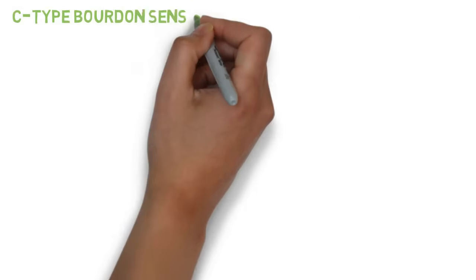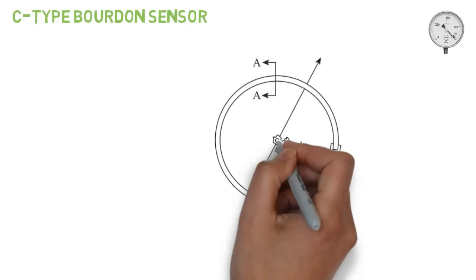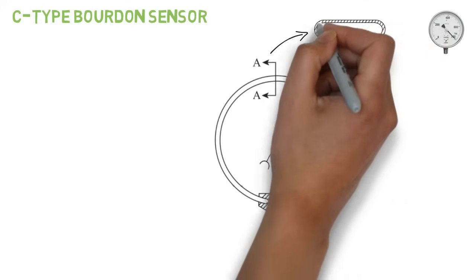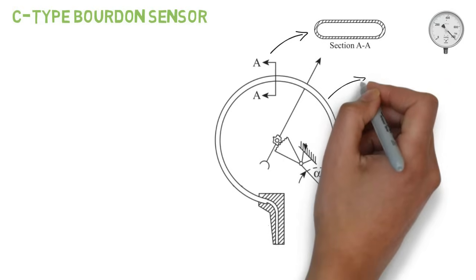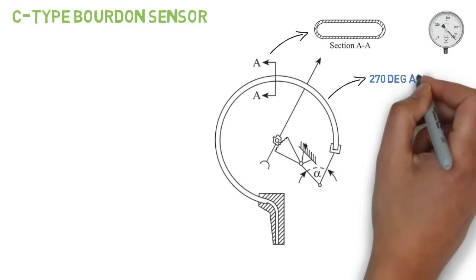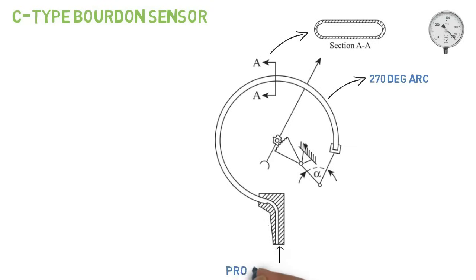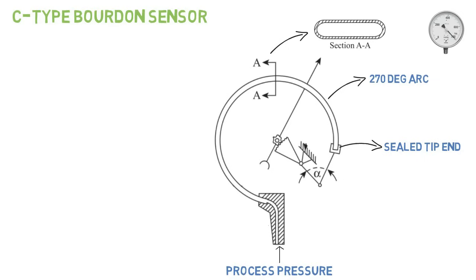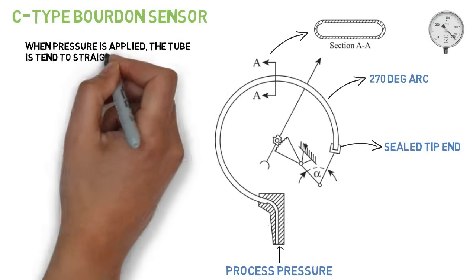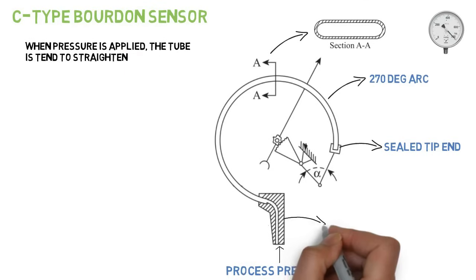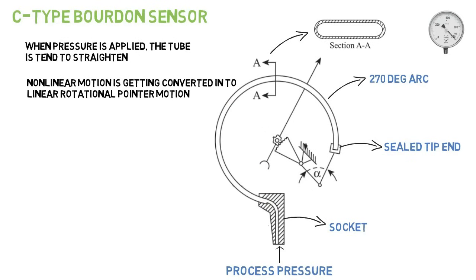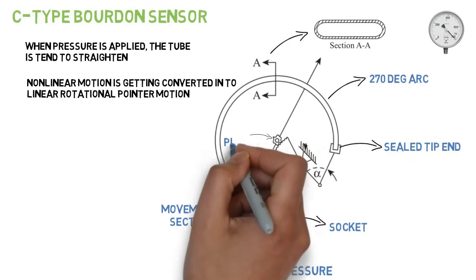C type Bourdon tube usually has an arc of 270 degrees. The process pressure is connected to the tube support end, while the tip end is sealed. When pressure is applied, the tube tends to straighten. The resulting tip motion is non-linear. This non-linear motion is converted into linear rotational pointer motion mechanically, by means of a geared sector and pinion movement through a connecting link.